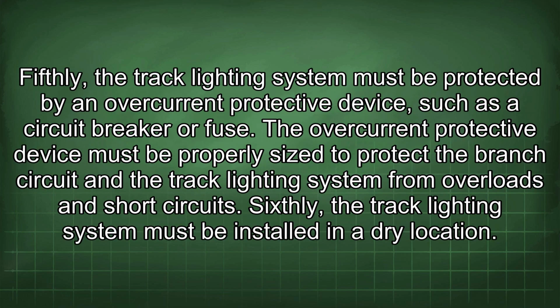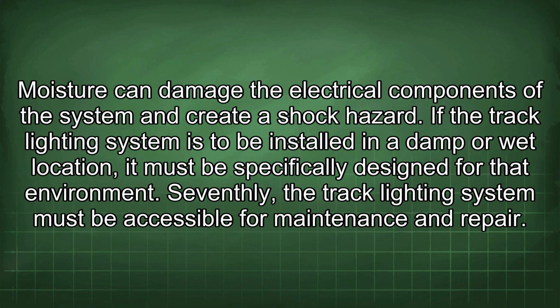Fifthly, the track lighting system must be protected by an overcurrent protective device, such as a circuit breaker or fuse. The overcurrent protective device must be properly sized to protect the branch circuit and the track lighting system from overloads and short circuits. Sixthly, the track lighting system must be installed in a dry location. Moisture can damage the electrical components of the system and create a shock hazard. If the track lighting system is to be installed in a damp or wet location, it must be specifically designed for that environment. Seventhly, the track lighting system must be accessible for maintenance and repair.